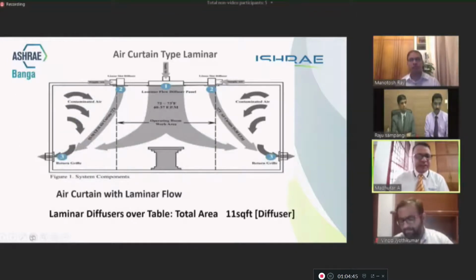This is the place where you generally have your return air. In a laminar flow operation theater, the supply air comes from the top. Preferably you have either a bigger area of HEPA filters, or one big HEPA filter in the center with two other areas adjacent, as per the OT design. So this air flows from the top of your diffuser, and the return air is taken at the bottom.